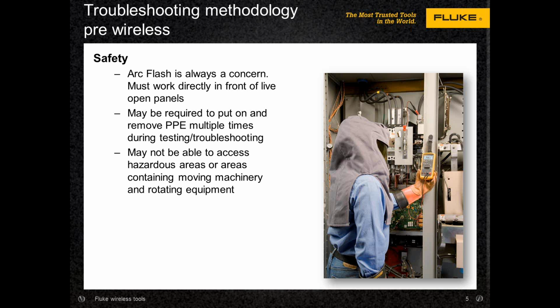The other thing is that you can see in the graphic that the technician in this case has an arc flash hood on his head, and that hood has a very tinted piece of plexiglass in front of them, and it's very difficult to see meter readings in some cases when you've got that hood on. So where the wireless really helps is that you can hook up the modules, either powered down or powered up, and then you can back away, take your hood off, get out of the flash protection boundary, and then you can see the meter readings while you're not in front of that panel and do whatever you need.